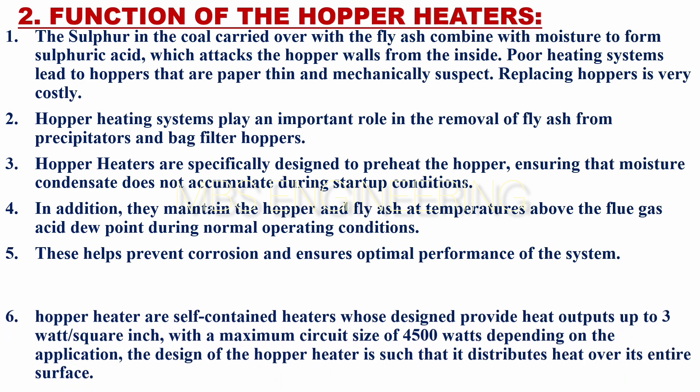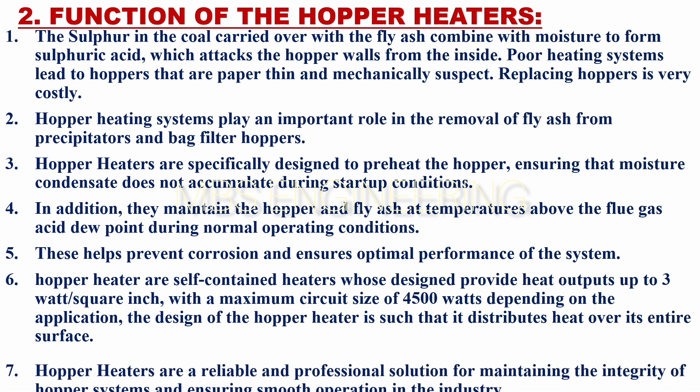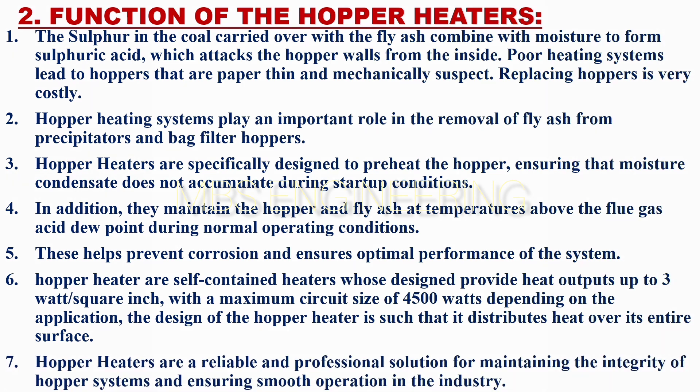The hopper heaters are self-contained heaters whose designs provide heat outputs up to 3 watts per square inch, with a maximum circuit size of 4500 watts depending on the application. The design of the hopper heater is such that it distributes heat over its entire surface. Hopper heaters are a reliable and professional solution for maintaining the integrity of hopper systems and ensuring smooth operation in the industry.